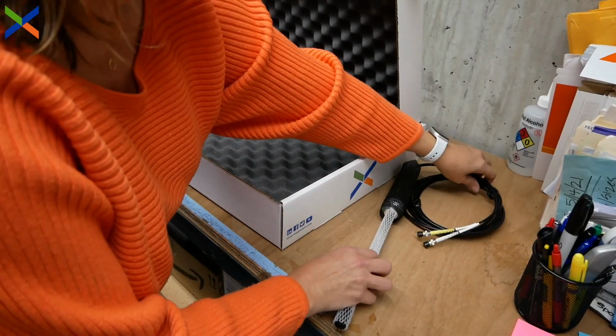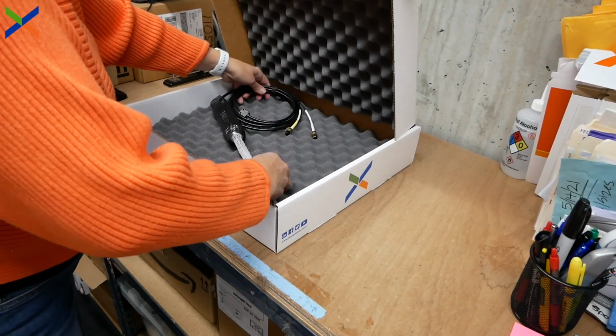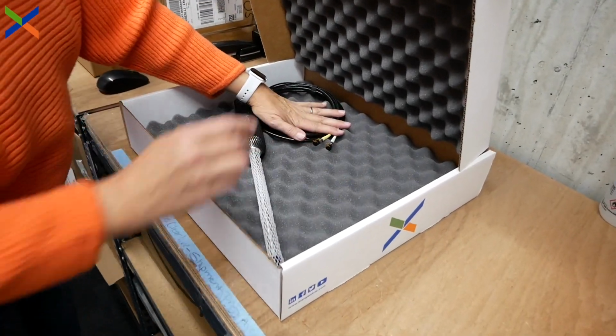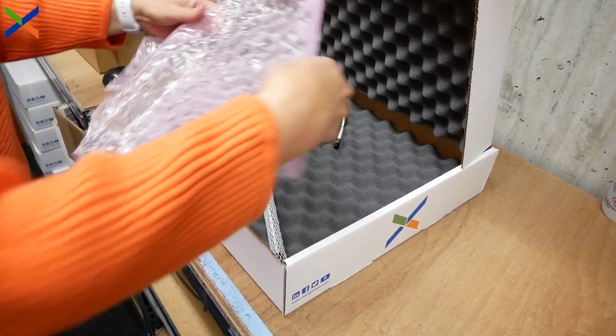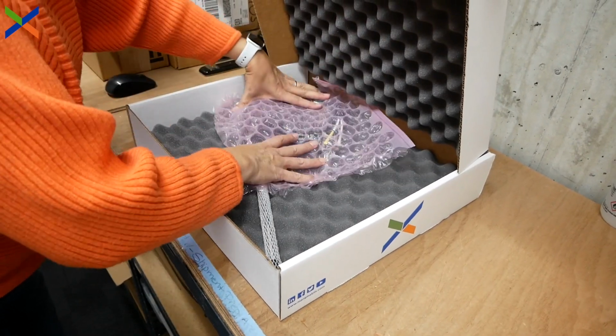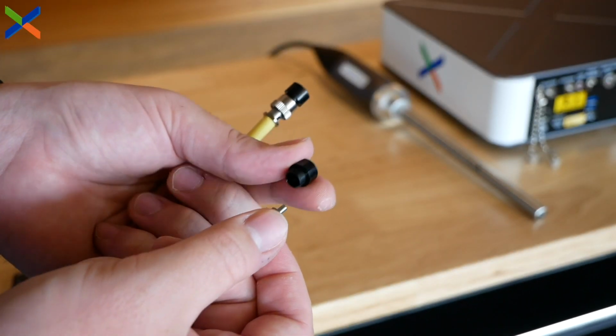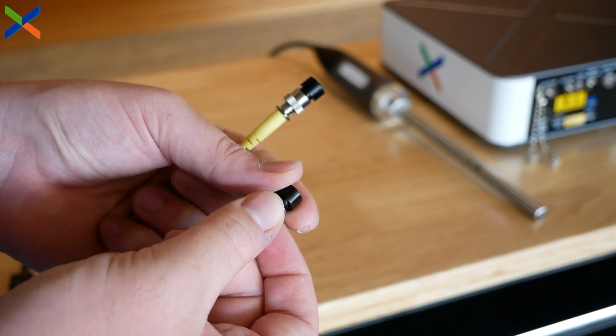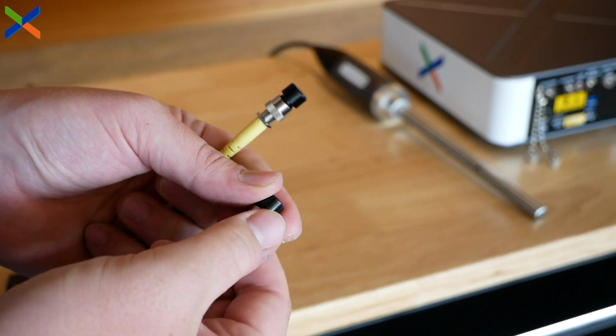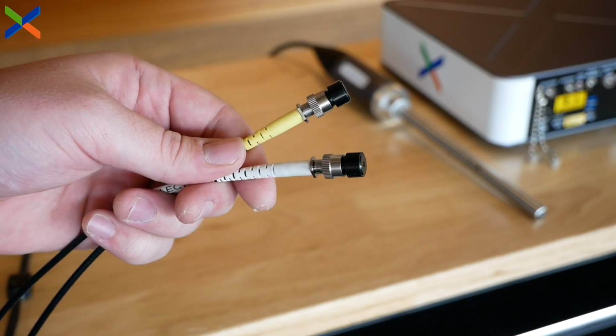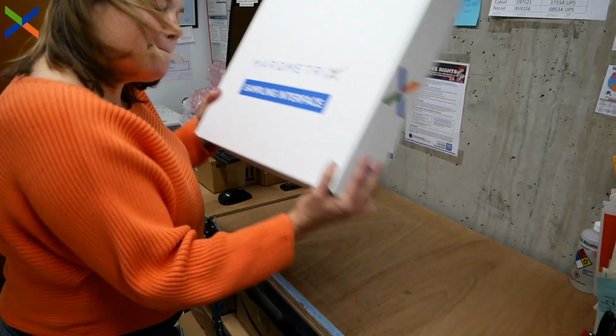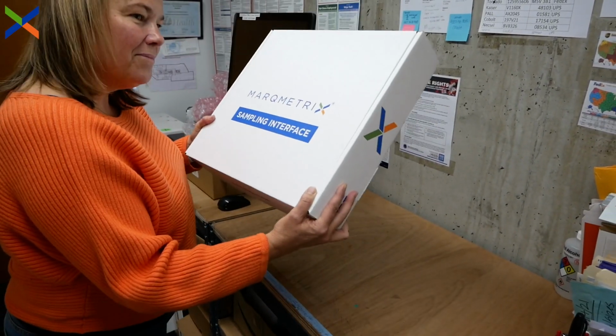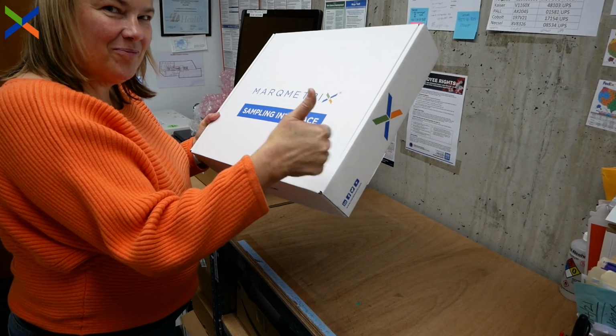If you are shipping a probe for maintenance as well, carefully place the fiber head and the probe in the small white box. Be careful not to sharply bend or kink the fiber cables. If available, secure the plastic dust caps to the fiber ends to protect the connections from damage. You can check that the fiber head and probe are secured by giving the box a shake. If you don't hear anything, the box is properly packed.